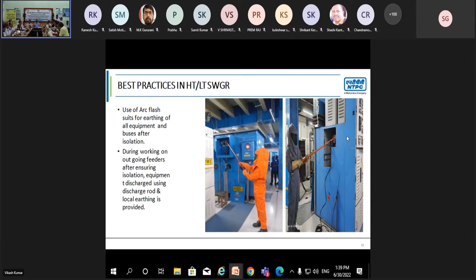For all these procedures, we ensure the use of PPEs. As has been shown in the slides as well, we are using arc flash suits in both HT and LT switchgears. We have different ratings for HT and LT: 40 joules per centimeter square for HT, and 8 joules per centimeter square for LT. It is as per the SOPs and the O&M safety rule book. So we are following that, and only after discharging the equipment of any stray voltages do we start working on that switchgear or equipment.